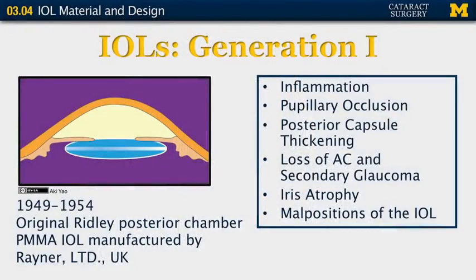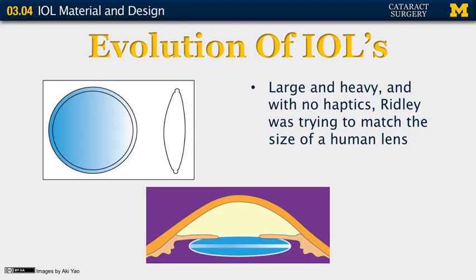This first lens lacked haptics and was associated with some problems. Patients tended to have chronic inflammation in the eye, and because it lacked haptics, there was occasionally occlusion of the pupil. There was significant posterior capsular thickening noted in many of the patients, and iris atrophy and general malpositions of the lens implant occurred over time. Here is a diagram showing the first Ridley lens. You'll see that it is round and again it lacks haptics. The lens was particularly heavy relative to a natural lens as well.